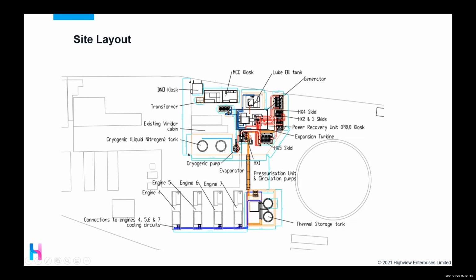So here we have our Lin storage vessels, which were storing the liquid nitrogen at 10 bar. We have a cryogenic pump here, which pumped it to the right pressure of 120 bar at nominal design point. Then we had our turbine hall here, which comprises a generator coupled to a 4-stage radial turbine. So outside we have our lube oil skid, providing lube for the bearings. We have an MCC kiosk, which has our PLC and our MCCs, and this is connected to a medium voltage cabin with switchgear.